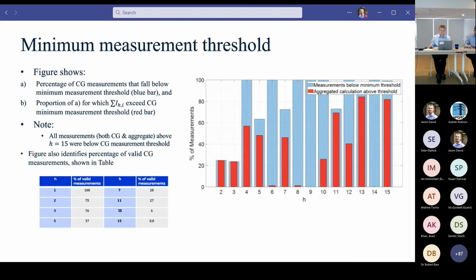We can't say exactly what the level of diversity is because we don't have a valid measurement for the collector group, but we can say there is a significant amount of diversity occurring, because the aggregation of the individual sources suggests there should be a substantial amount of current going through the cable. So this will hopefully become a little clearer in a couple of slides. There's also a publication on this if it's of interest to you.